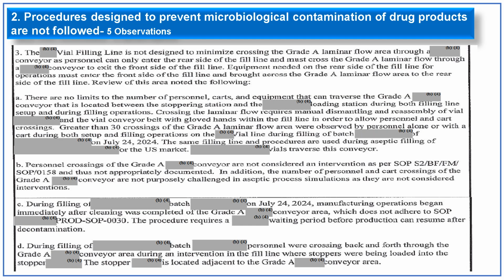The third observation under the second 483: the vial filling line is not designed to minimize crossing the grade A laminar airflow through the conveyor, as personnel can only enter the rear side of the filling line and must cross the grade A laminar flow conveyor to exit the front side of the fill line. Equipment needed on the rear side of the fill line operations must enter the front side and be brought across the grade A laminar airflow area to the rear side. So there were around 4 observations made for this.